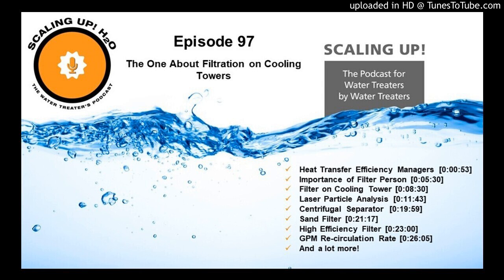So the total suspended solids in a cooling water system is not all that clear on what's going on. You want to know what the total suspended solids are, but in most cooling towers, the solids are low because almost everything in the water is very fine, less than 5 microns, and it's usually softer material. So you don't get much TSS on a cooling tower. If you've got contamination from a process, if you've got river water makeup, then you're going to get a lot of TSS.